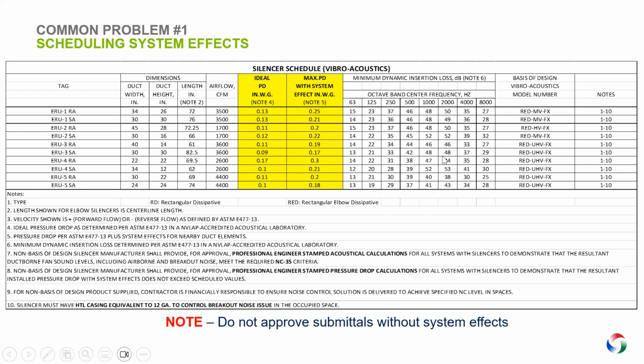And that's why whenever we provide the schedule on the silencer, we always show two pressure drops. One is ideal pressure drop and second is system effect pressure drop. And we do provide all the calculations to stand behind it in terms of pressure drop and acoustical calculations as well. So always look into pressure drop with system effect on your submittals.